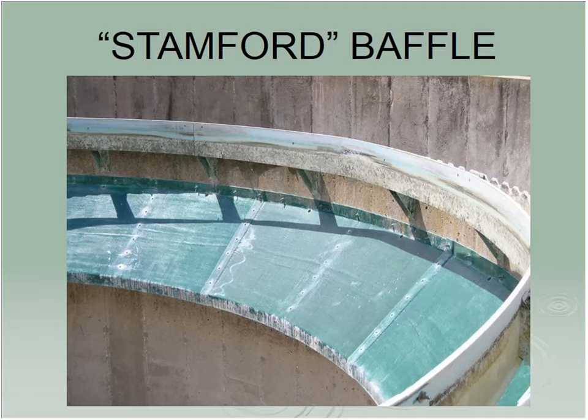So the Stamford baffle, it's actually the Crosby baffle. Dr. Crosby came up with this design, but he was working at Stanford, so it incorporated that title. Put this slope addition along the wall, so if that material came across the bottom of the tank and came up the wall, it would hit this, have to return back towards the center before it could head towards the effluent weir, again trying to keep it in that much longer so the solids would actually drop out.